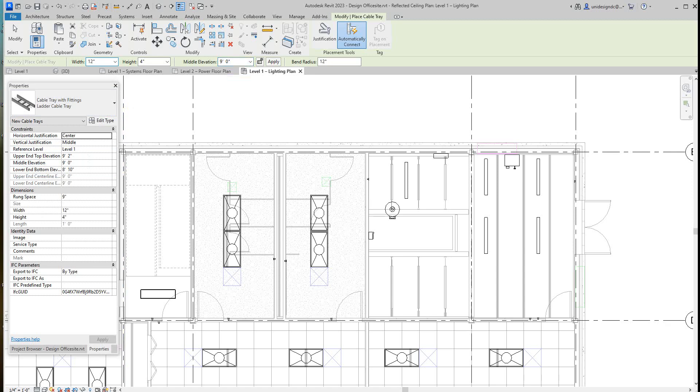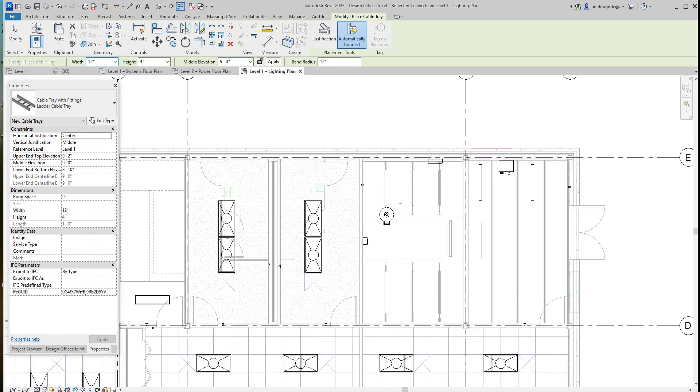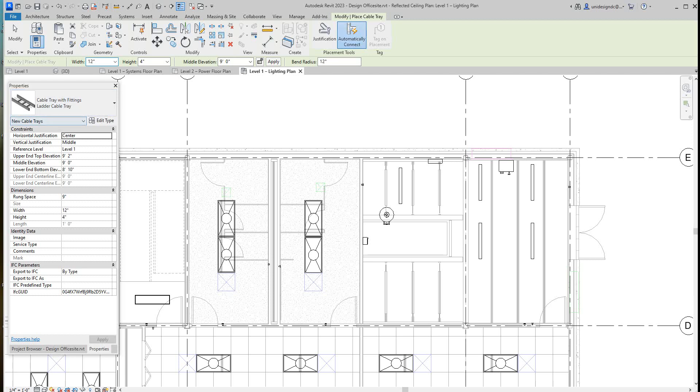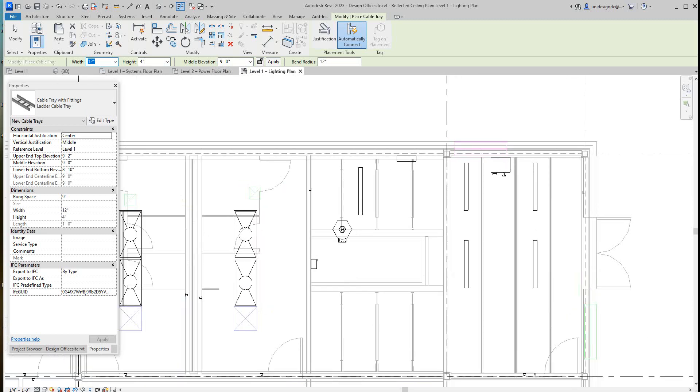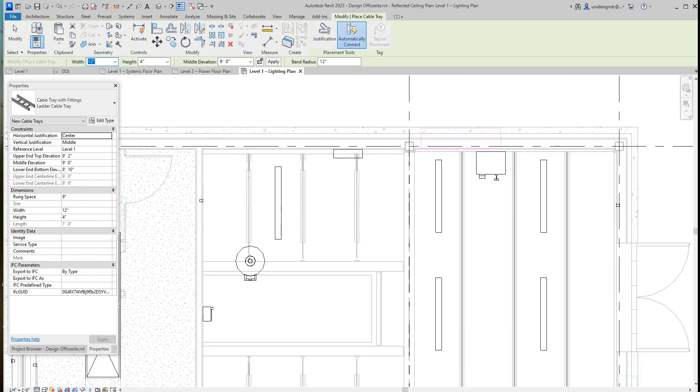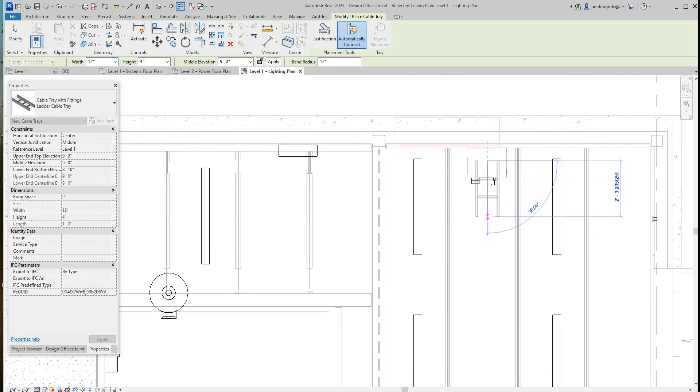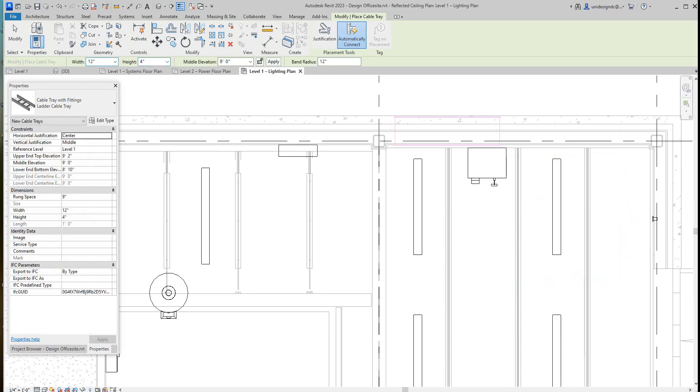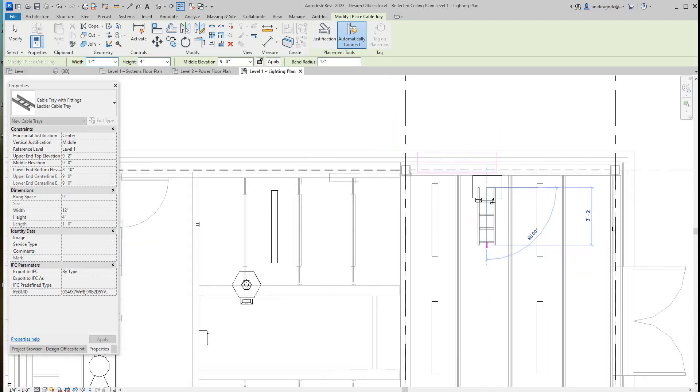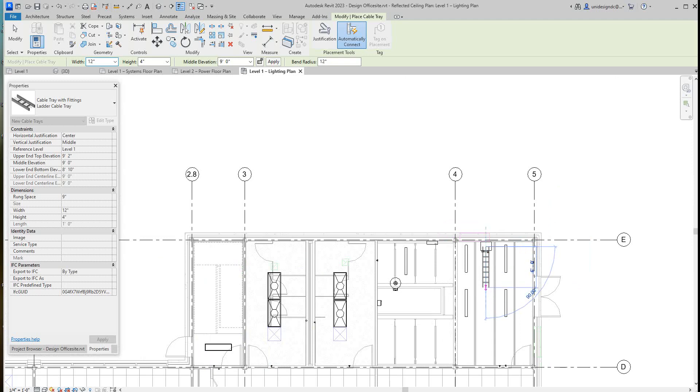I don't know what I'm going to use because you've got other obstacles. So this is the fun part when it comes to modeling and routing cable trays - there's a lot going on. Basically you've got an automatic connector on it. I'm going to select this cable tray and here in the taskbar, it's a 12 inch width, four inch height, and it's at elevation nine foot. For now let's leave it at 12. Now I've got an automatic connector on here and this piece of equipment should take it. This is a motor control center. I think it did it. Let me just try that once more. Yeah, so it's accepted it. What I'm going to do, I'm going to just place it here and drag it up to this point. And I'm going to cancel.